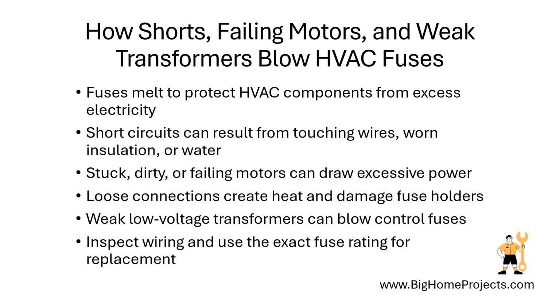failures. One lesser-known cause is a weak low-voltage transformer, which can blow the small control fuse even when the larger equipment seems to work normally. To troubleshoot safely, turn off power, look for burned wires or wet areas, and check whether the fuse size matches the label on the equipment.